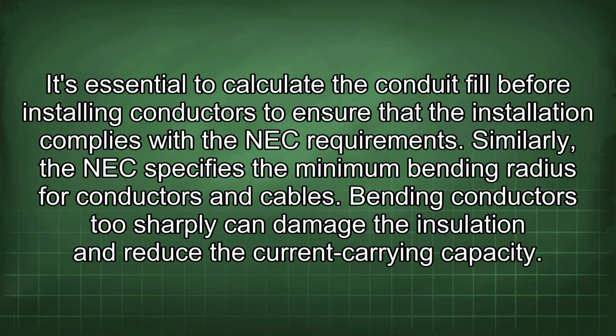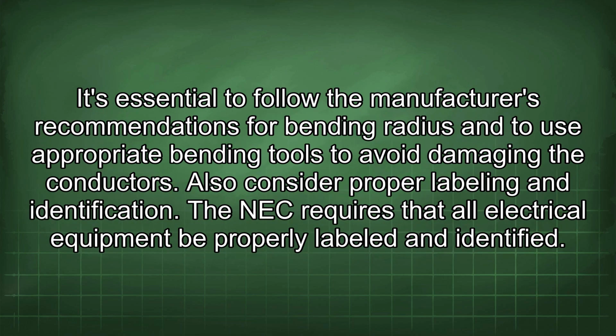Similarly, the NEC specifies the minimum bending radius for conductors and cables. Bending conductors too sharply can damage the insulation and reduce the current carrying capacity. It's essential to follow the manufacturer's recommendations for bending radius and to use appropriate bending tools to avoid damaging the conductors. Also consider proper labeling and identification.